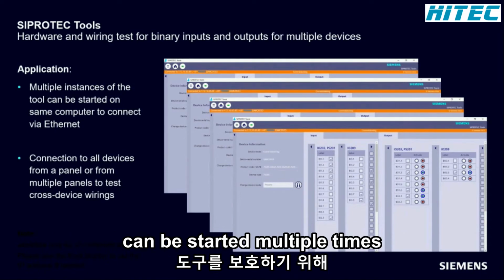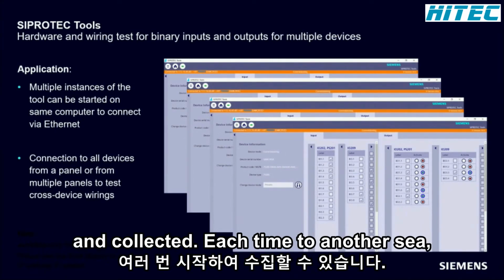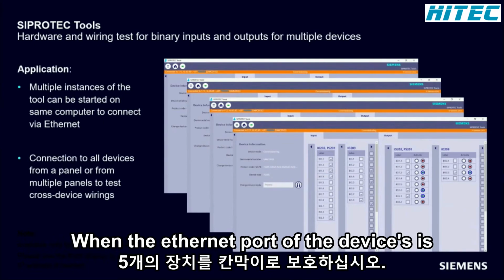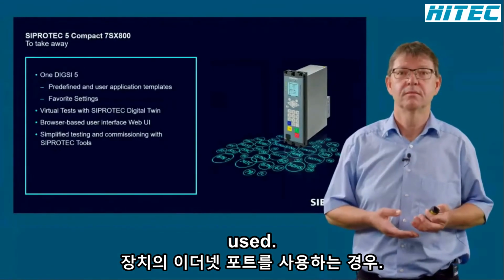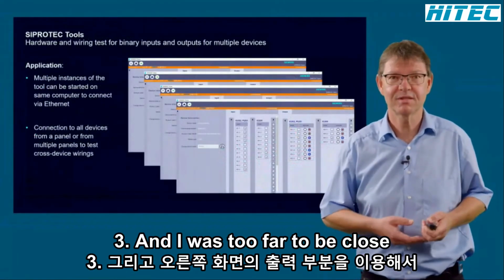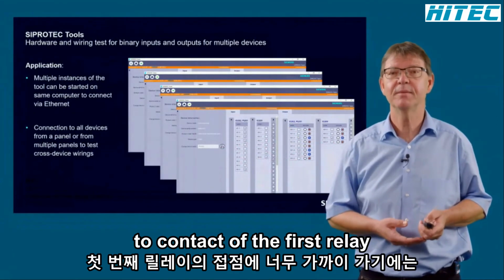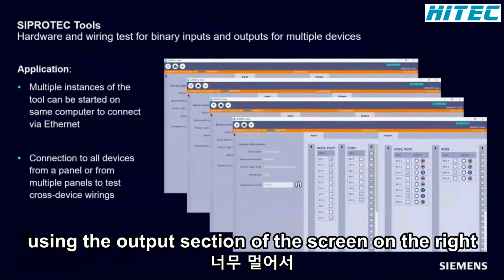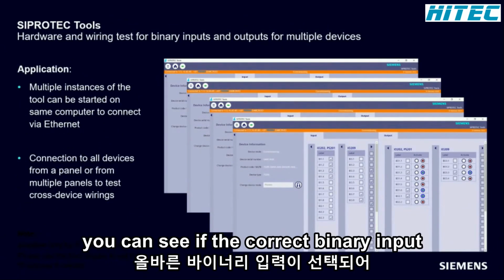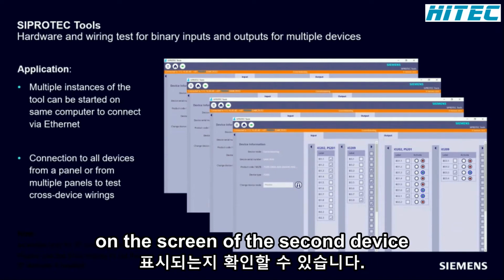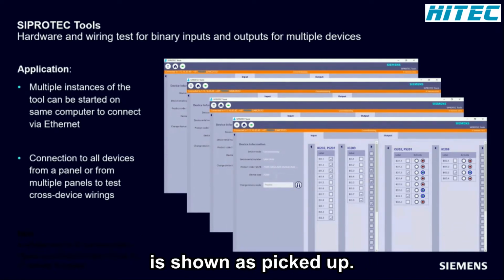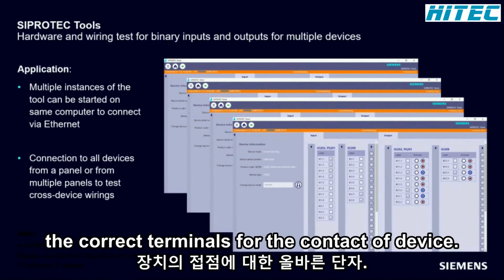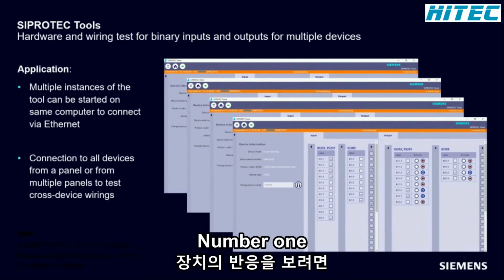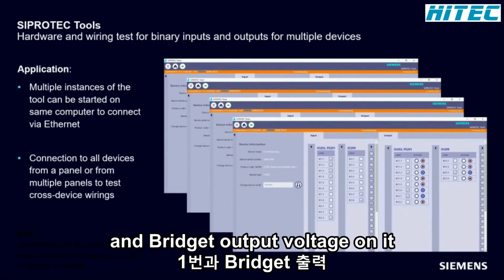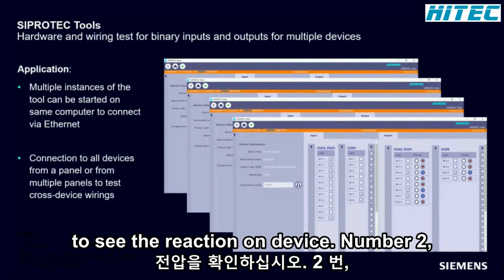SIPROTEC tools can be started multiple times and connected each time to another SIPROTEC 5 device in the cubicle when the Ethernet port of the devices is used. Sorry, I was too fast. Simply close the contact of the first relay using the output section of the screen on the right-hand side, and in no time, you can see if the correct binary input on the screen of the second device is shown as picked up. No need to go the tedious way and search the correct terminals for the contact of device number 1 and bridge it or put voltage on it to see the reaction on device number 2.